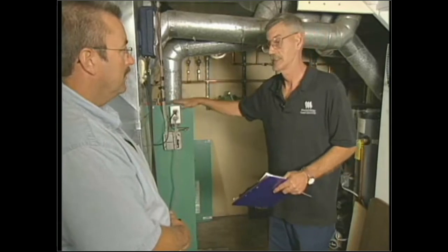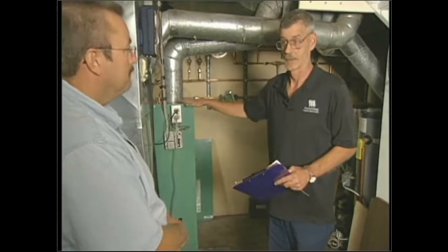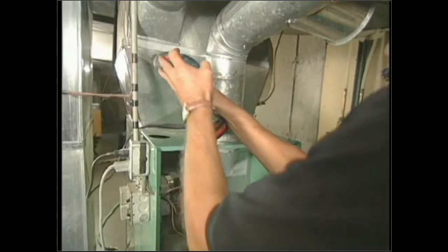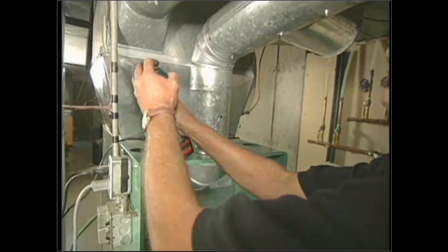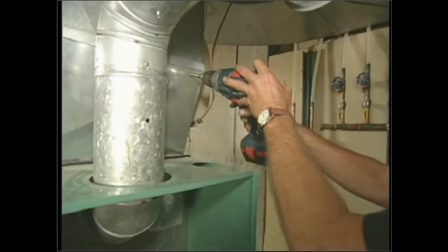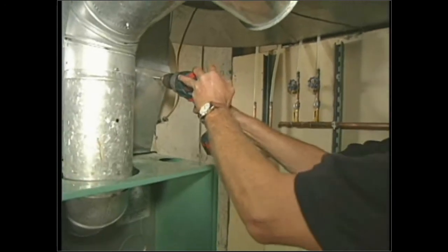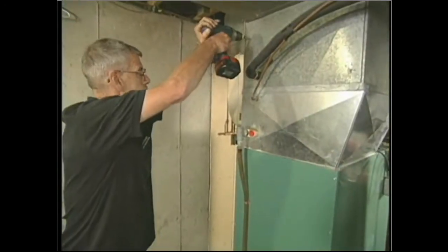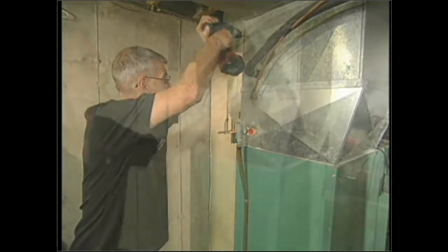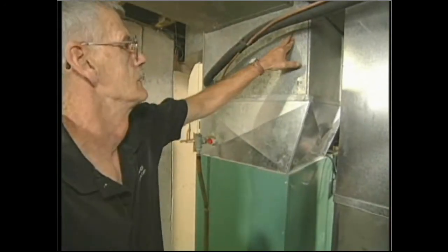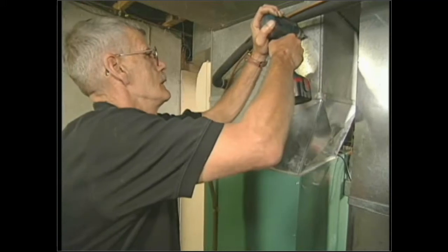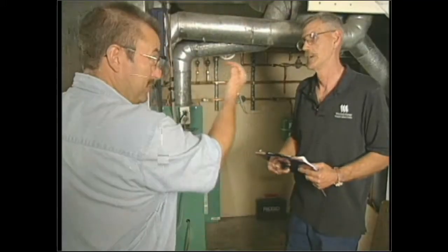As with all the other furnaces we tested, all the gas furnaces, we do the temperature rise on an oil furnace exactly the same way. We locate a plane all the way around our upper plenum where we can get 4 holes in. It's not crucial to always have them on that plane, but it's ideal. In this situation, since we have an A coil, we were able to get 2 on this side and 2 on the other side, and the ones on the other side are slightly higher. That's okay if you have a good explanation for why you're doing it. In the perfect world, they'd be on that same plane. And we're always concerned about the A coil. We don't want to damage it.